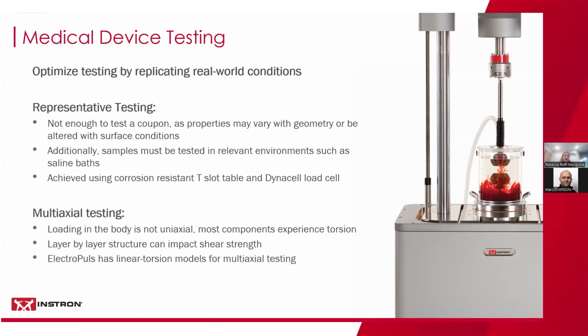So that is the samples, and then we move on to the axis. As I mentioned, representative conditions for medical devices are unfortunately not just uniaxial, they are multi-axial, and most components will experience torsion. And in fact, often that torsional axis is the weaker part.